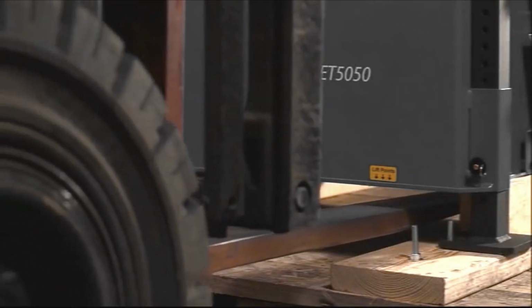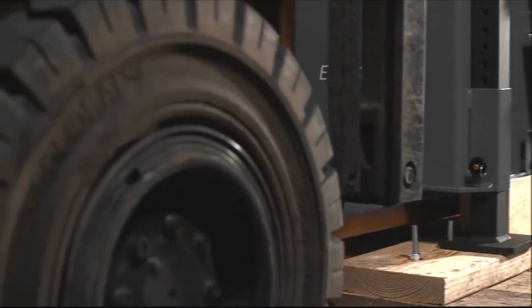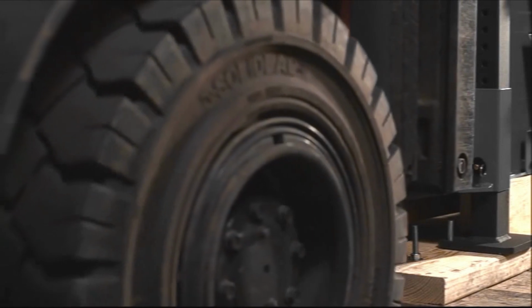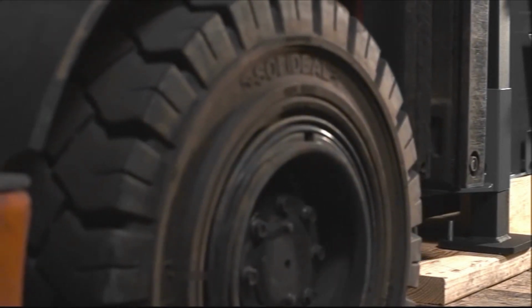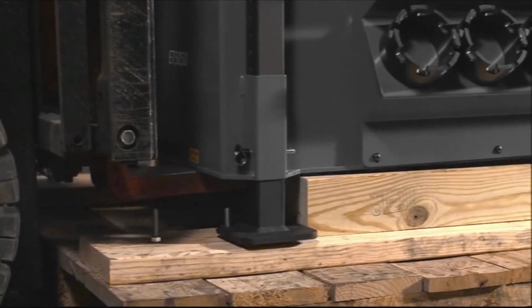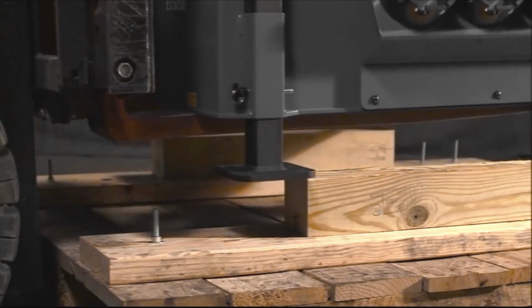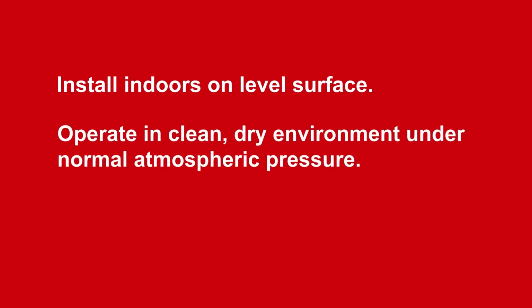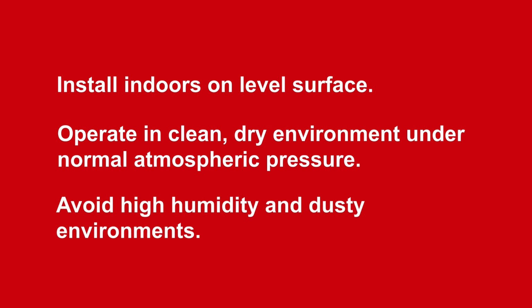Prior to any move, identify lift points on the machine. Lifting at these lift points, ensure that the load is evenly distributed on the forklift. Always position the front of the ET5050 close to the front wheels of the forklift. The machine should be installed indoors on a level surface and operated in a clean, dry environment under normal atmospheric pressure. Avoid high humidity and dusty environments.